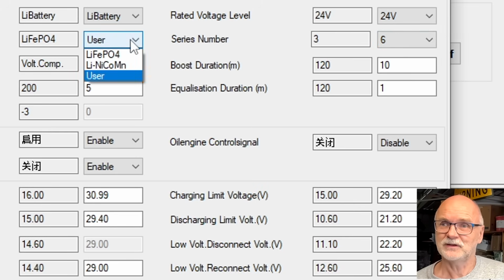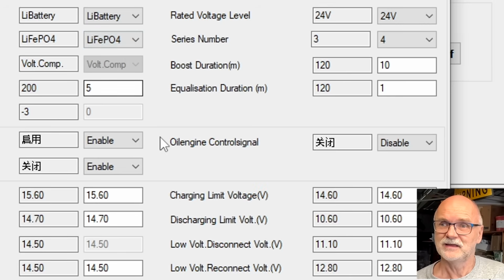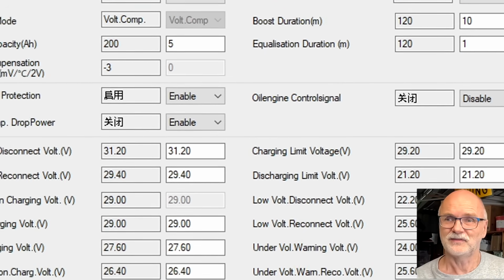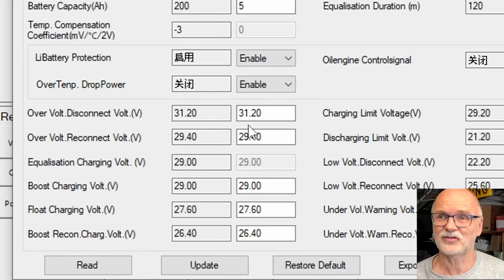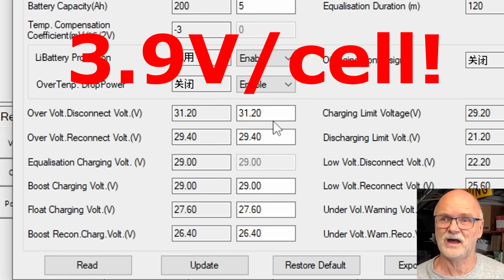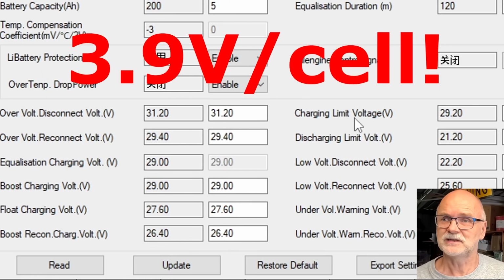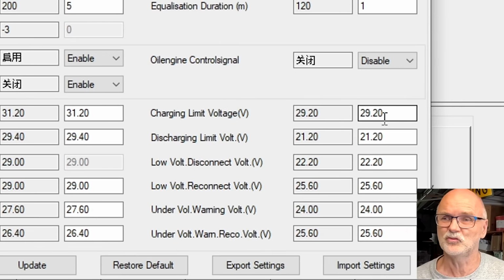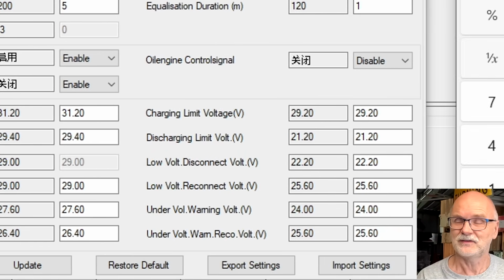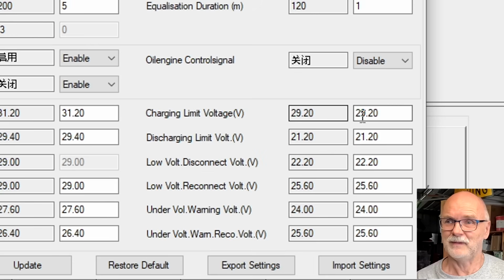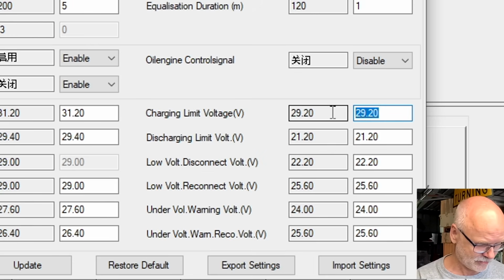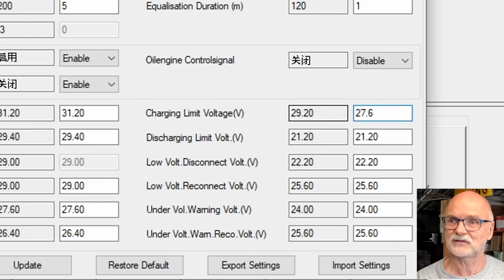Unless I change this one to lithium iron phosphate, but I don't like the settings. Then I can say we've got 8 cells for a 24 volt system, but the overvoltage disconnect is at 31.2 volts — this is far too high. And the charge limit voltage is at 29.2, this is too high either, that's 3.65 per cell. I don't want to charge that much, I want this one on 27.6.